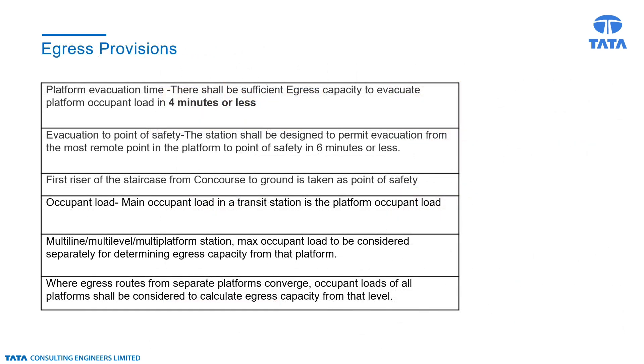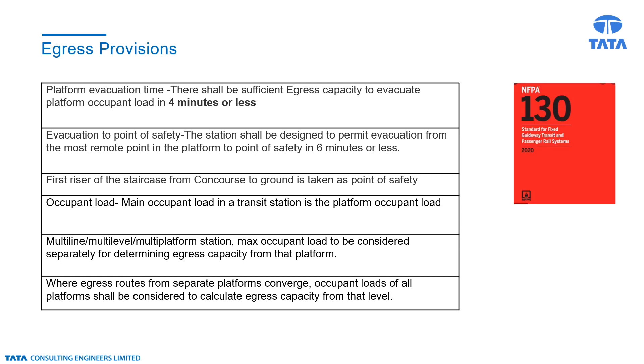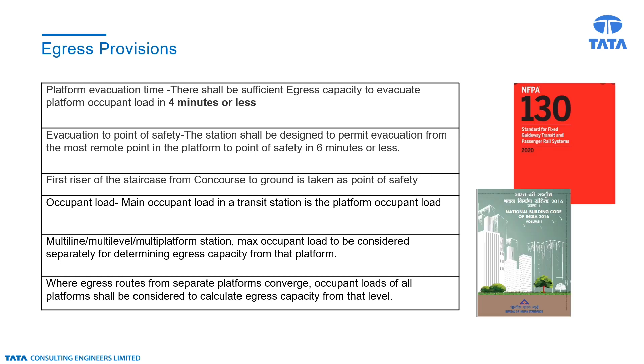Station design shall allow safe evacuation of occupants in an emergency. For egress and evacuation measures, the requirements as provided in NFPA 130 and NBC 2016 shall be followed. There shall be sufficient egress capacity to evacuate platform occupant load in four minutes or less. The station shall be designed to permit evacuation from the most remote point on the platform to a point of safety in six minutes or less.